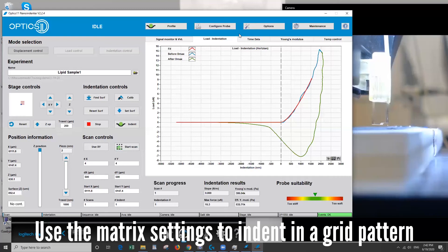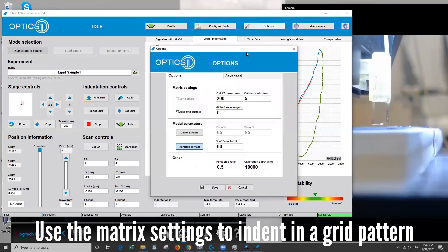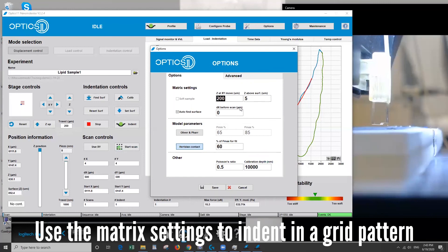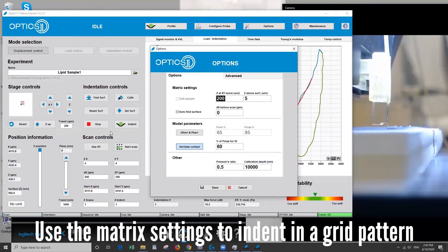And then come here to options and make sure that your probe is being raised high enough that when it moves 500 in the X direction it does not crash into any part of your sample. And this could be due to the sample has some kind of tilt to it. It could be that it's rough or uneven. And so you basically want to clear anything that could crash, especially because you're letting the instrument do this in an automated fashion.